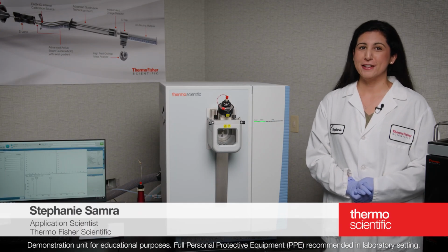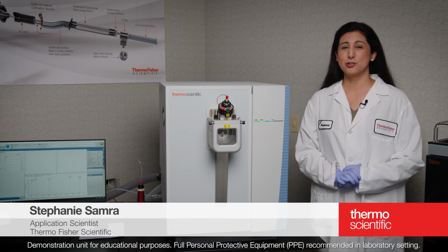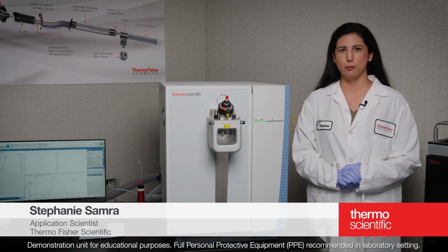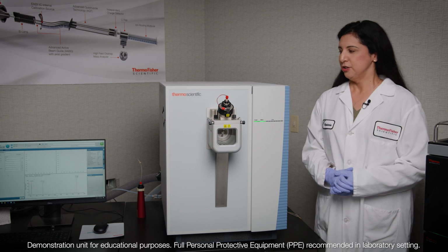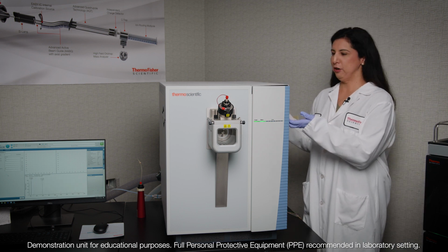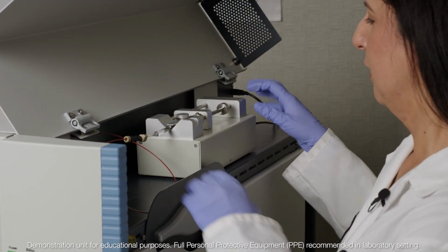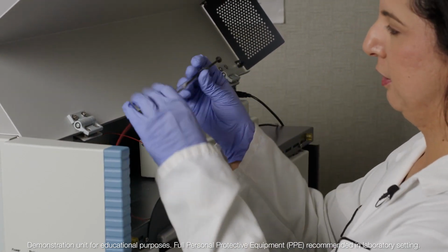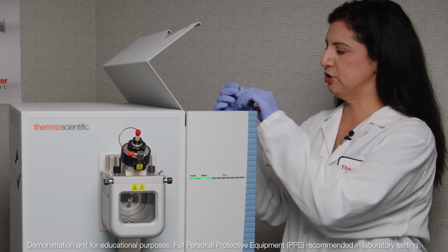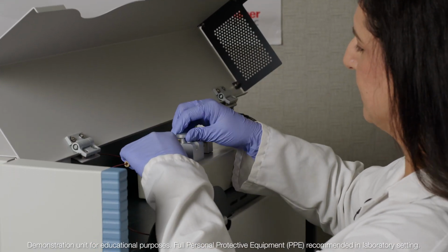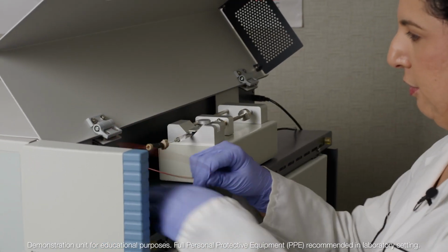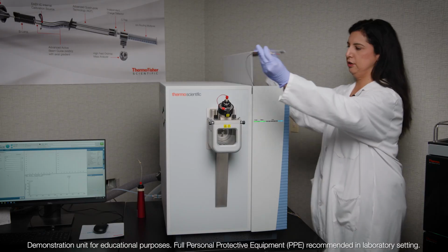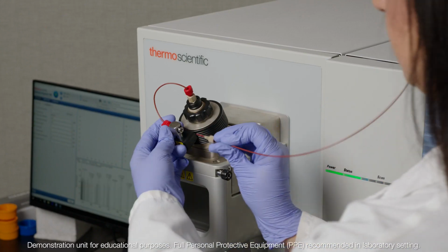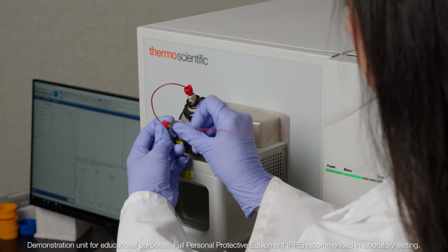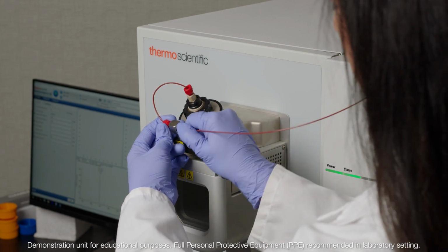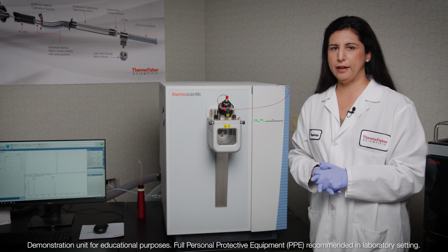Next, I want to show you mass calibration, and this is something that has been made so much easier on this generation of Orbitrap instruments, the Exploris. So we have this hidden compartment here where we have the syringe pump, and we can go ahead and load up our syringe with calibration solution. Lock this into place. Go ahead and grab the tubing, close the door, connect it to the source housing, tighten it up here, and then go over to our instrument to go ahead and calibrate.